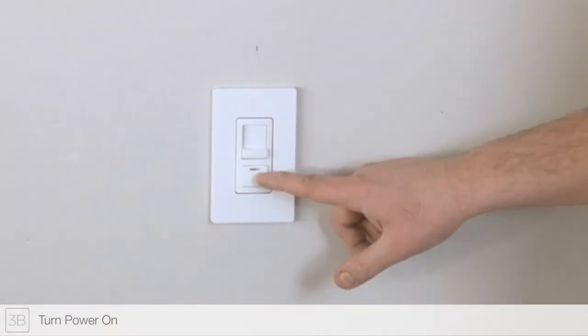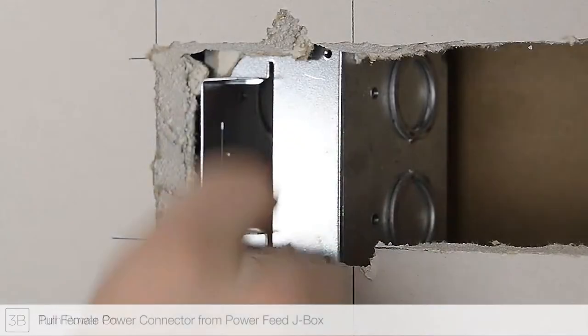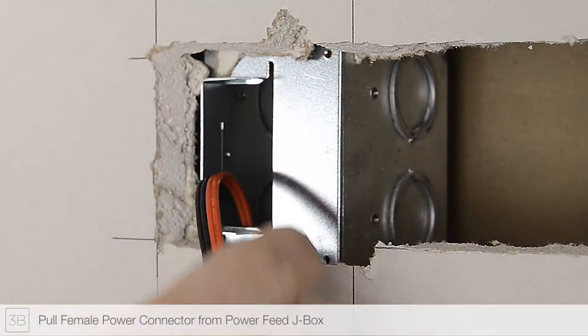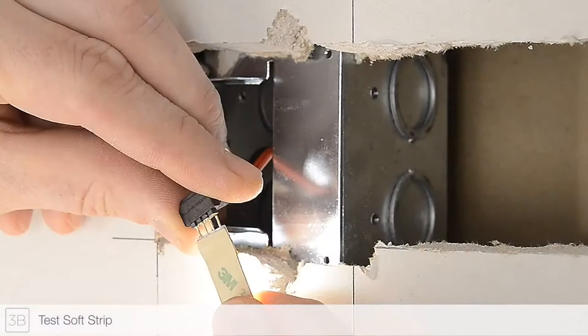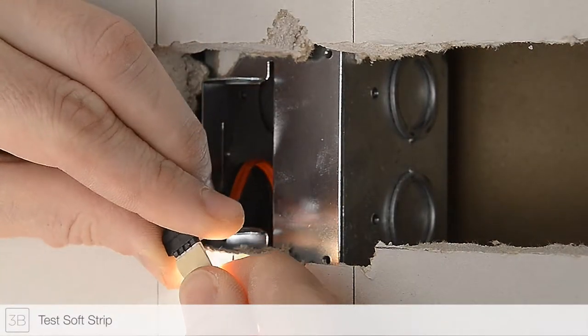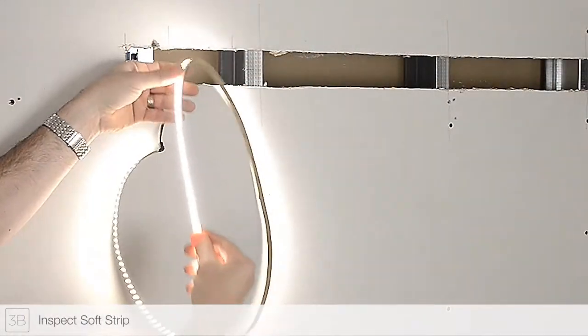Step 3B: Restore power to the junction box to test the LED soft strip. It is important to align the plus 24 VDC marking on the soft strip with the red wires of the power feed cable. Inspect the strip for any irregularities before continuing.